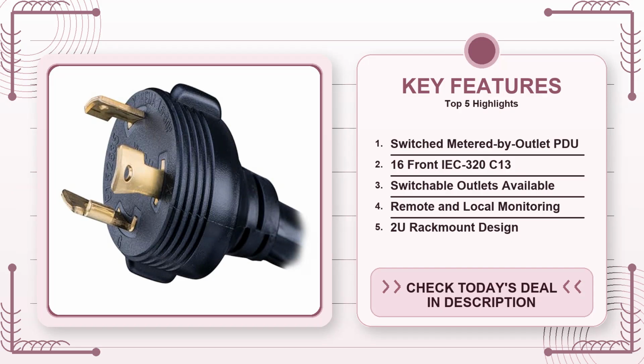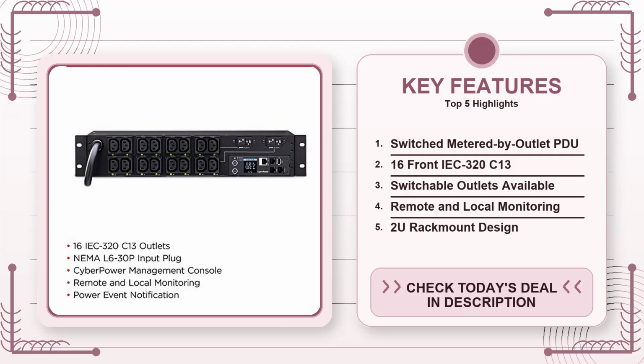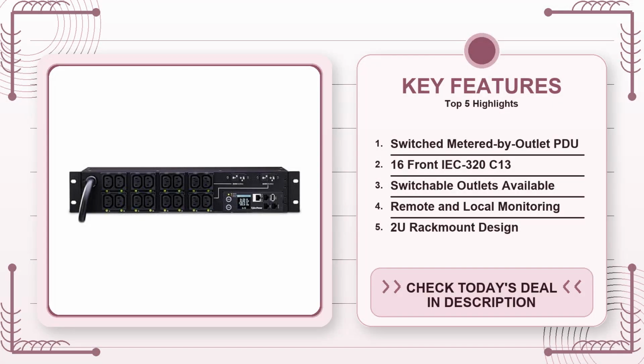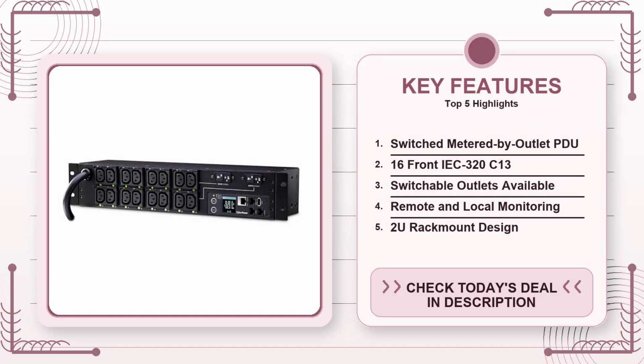The PDU81007 offers switched, metered-by-outlet capability, meaning you can turn any of the 16 front-facing IEC-C13 sockets on or off either locally via the front panel switches or remotely through a web interface or SNMP. That level of granularity is something you normally only see in much larger, pricier units.